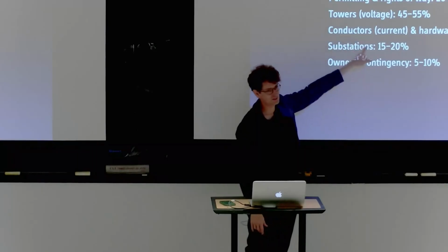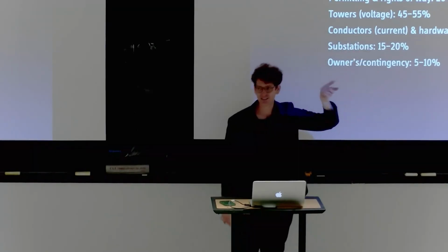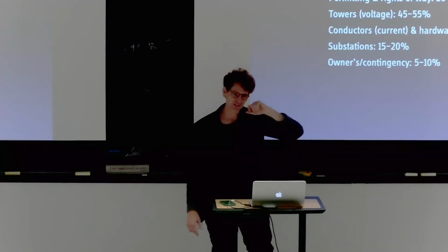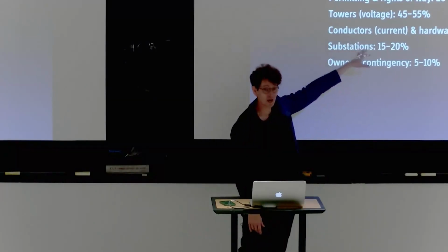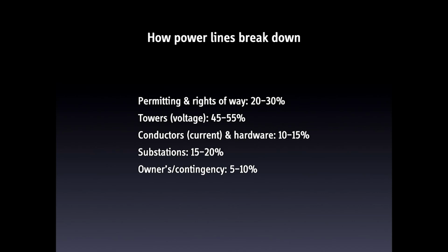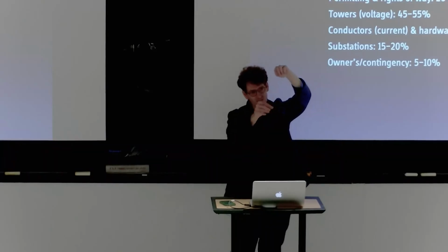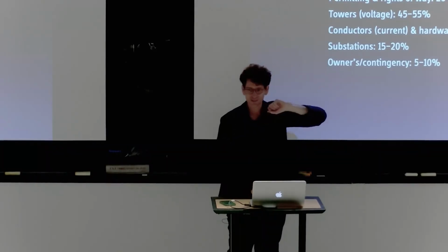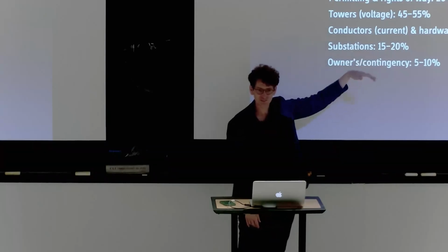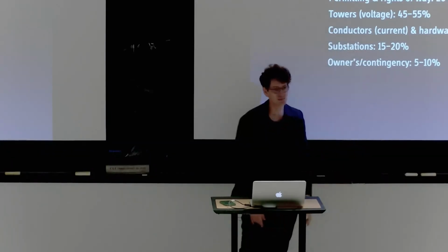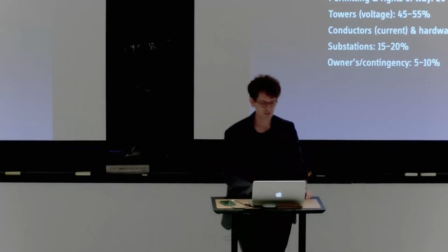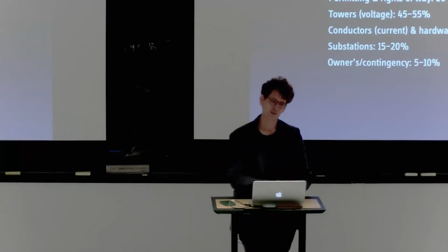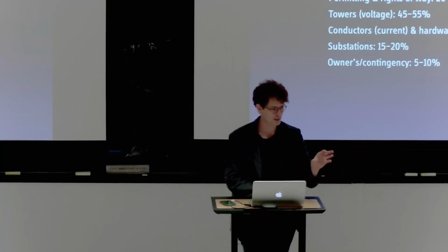The number of conductors you run on the tower determines the ampacity of the circuit, how much current you can send. You can triple the amount of power by tripling the amount of wires, as long as you have room on your towers to put more wires. So sometimes you'll see all these wires hanging in a row, and that's why. That doesn't cost very much to increase the ampacity, but it does cost if you want to change the voltage. So you have this weird phenomenon where the voltage is actually the determining factor in the cost of transmission, not the power that you're sending. Power is obviously the thing that you're using.